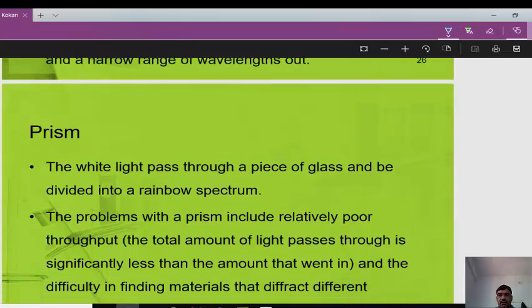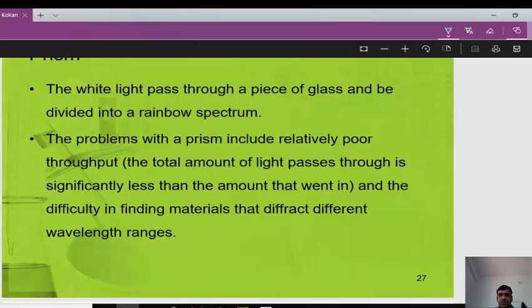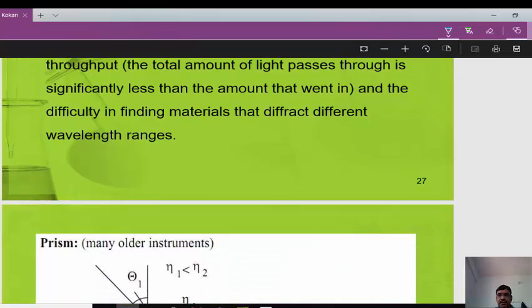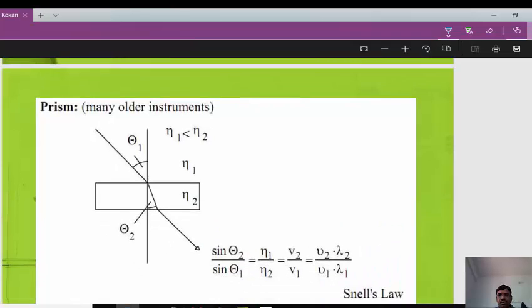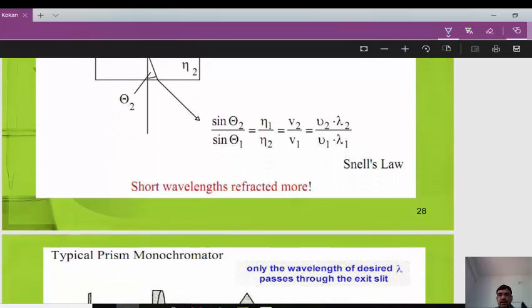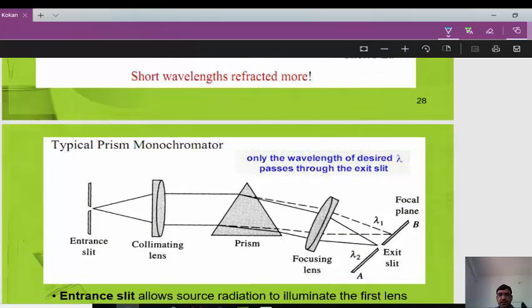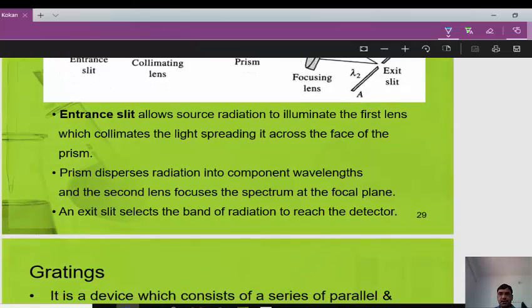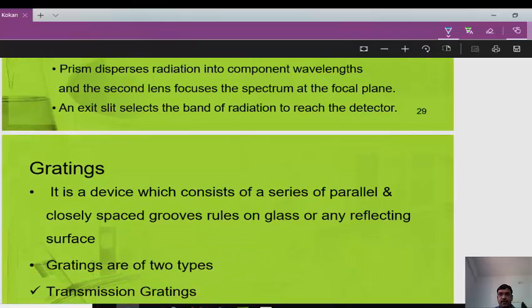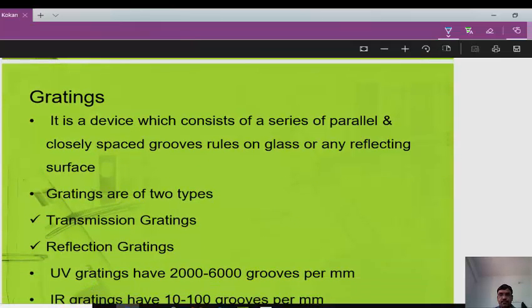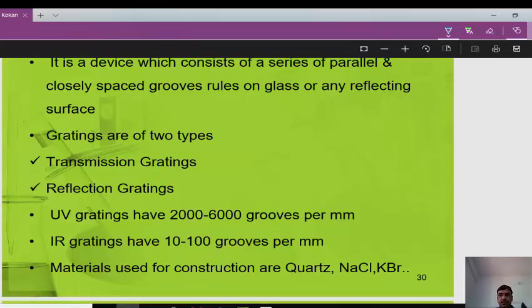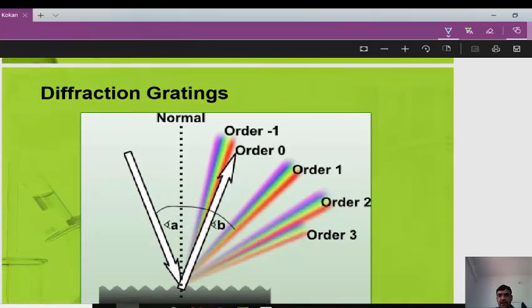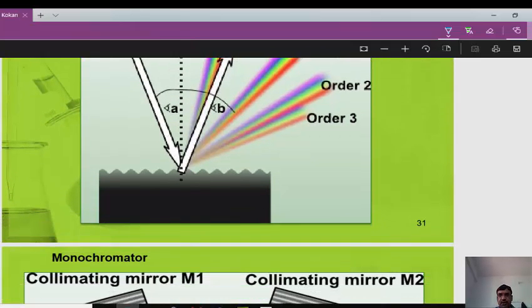Filters are simple sheets of plastic or glass that absorb unwanted wavelengths, passing only those required for analysis. Monochromators are far more complicated, comprising a series of optics inside a light-proof box with entry and exit slits. A prism separates white light into a rainbow spectrum, though it has relatively low output. A typical prism monochromator includes an entrance slit, collimating lens, prism, focusing lens, and exit slit. The entrance slit allows source radiation to illuminate the first lens.